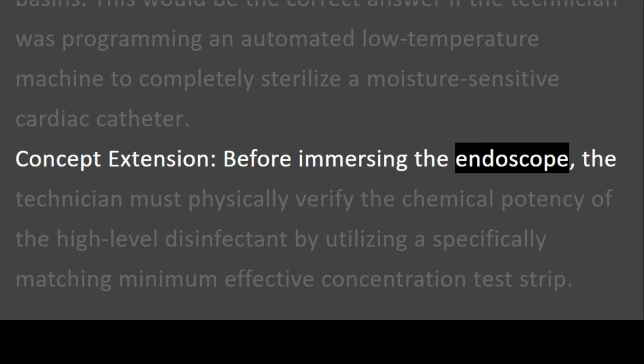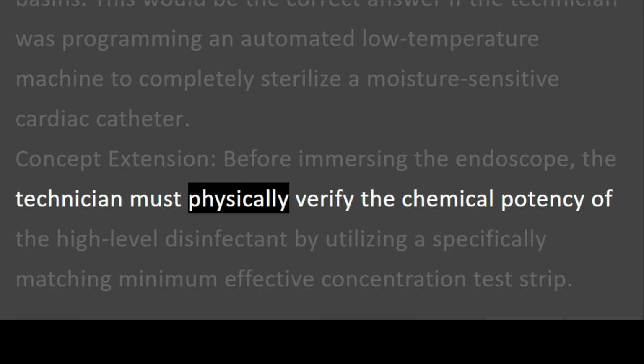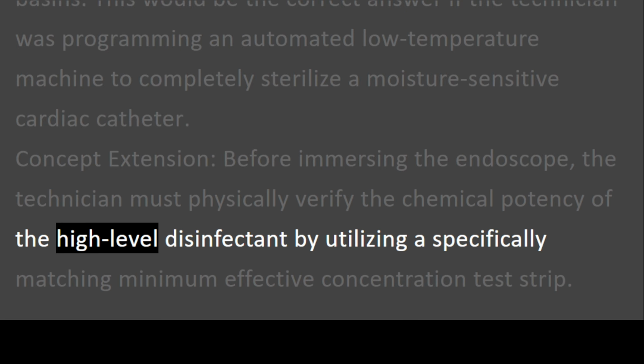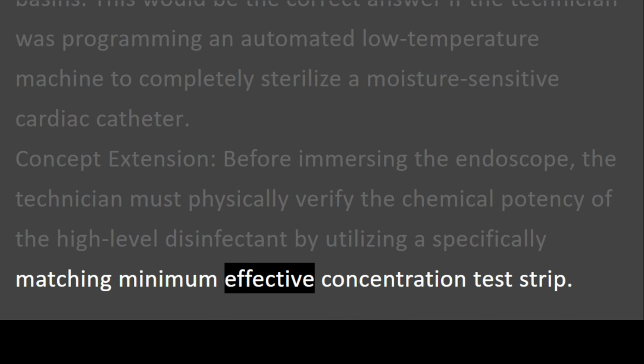Before immersing the endoscope, the technician must physically verify the chemical potency of the high-level disinfectant by utilizing a specifically matching minimum effective concentration test strip.